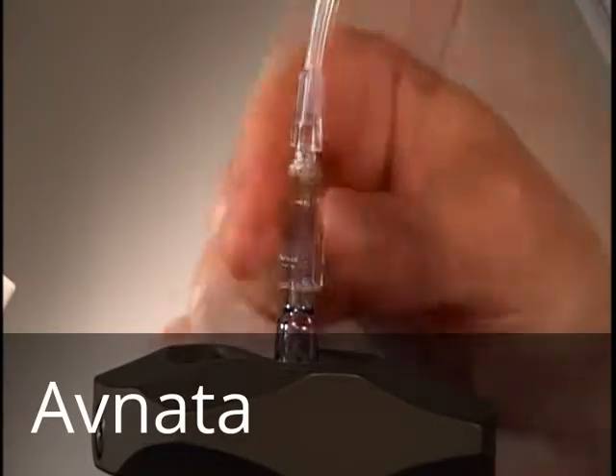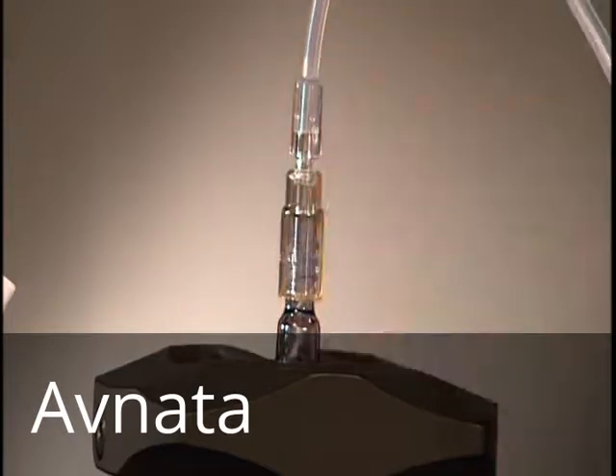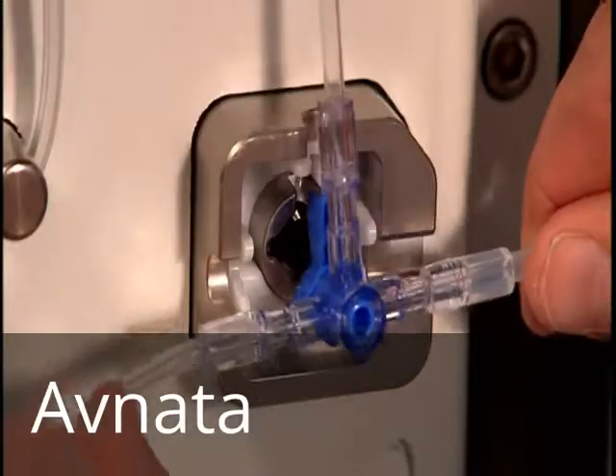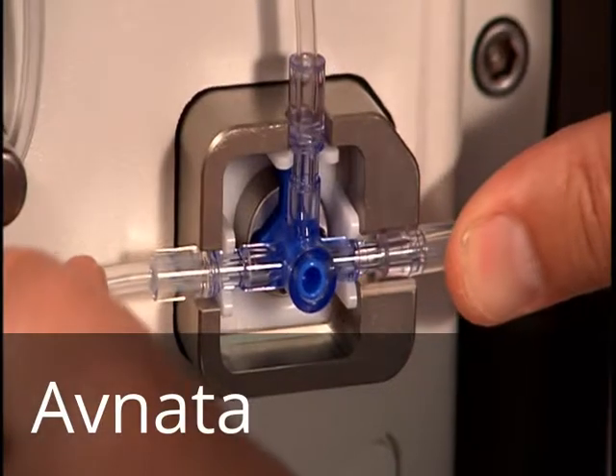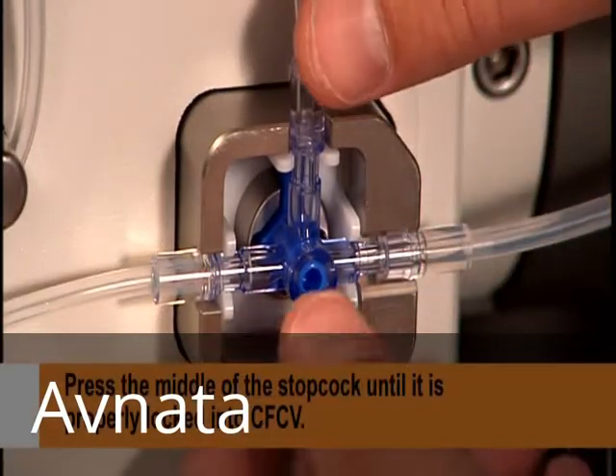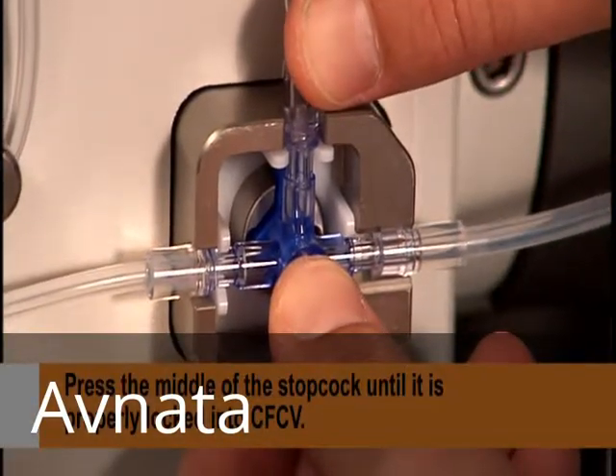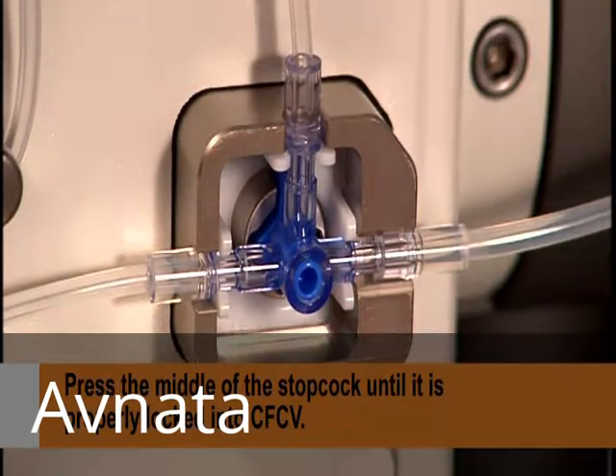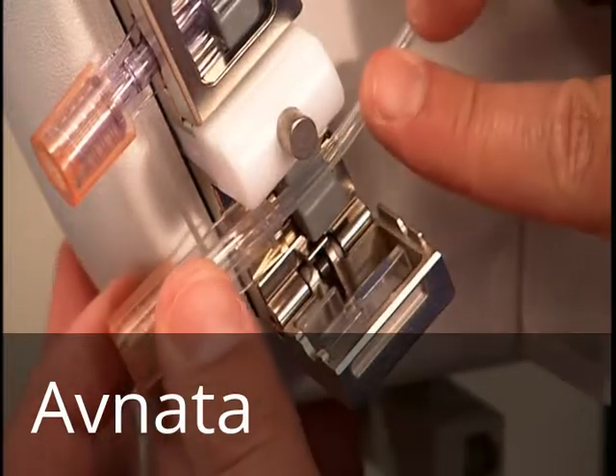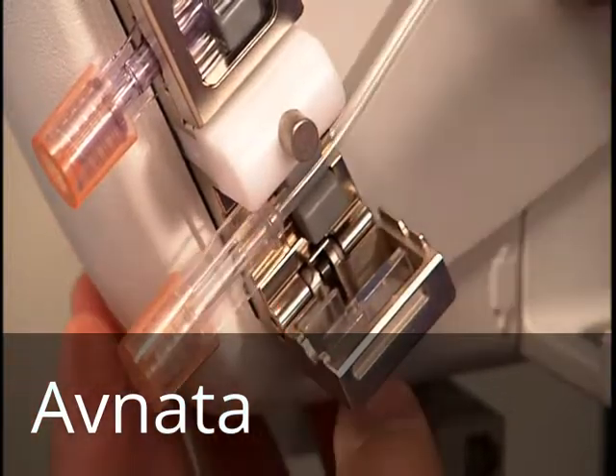Step 2. Connect the tubing to the syringe. Step 3. Install the stopcock into the contrast flow control valve. Press the middle of the stopcock to ensure that it is properly locked into the CFCV. Step 4. Insert the tubing connector into the gross air detector and close the door.